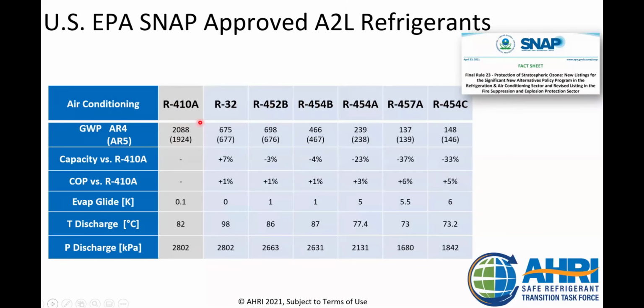As you can see, 410A has too high of a global warming potential, so it's out. The other ones are low enough so they can all be utilized. From a capacity standpoint, like how much energy can the refrigerant hold? Not the capacity of the equipment, because that's also a function of compressor and coil and fan and etc. But the actual refrigerant itself, R32 can hold a few more BTUs per pound than R410A could do, and R454B is a few BTUs less.